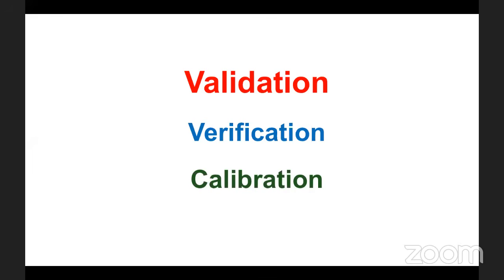accreditation body. And these analyzers shall be calibrated by the manufacturer or authorized distributor. And your analyzers, whether it is a hematology analyzer or biochemistry analyzer, where you are getting quantitative results, these shall be calibrated with the calibrator only. Sometimes some people say, we are comparing the result with a high-end model. No, that is not acceptable. It should be calibrated with the calibrator, and that calibrator is a sort of reagent where these analytes have a defined fixed value.